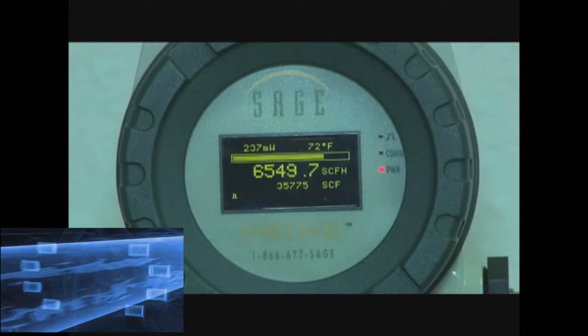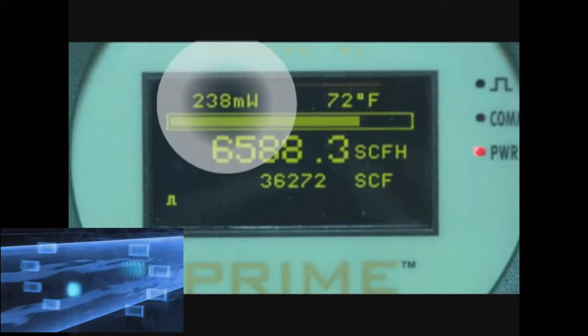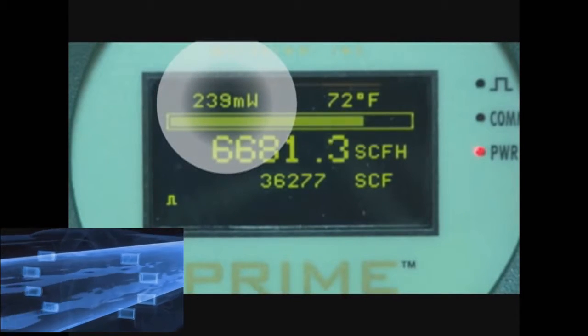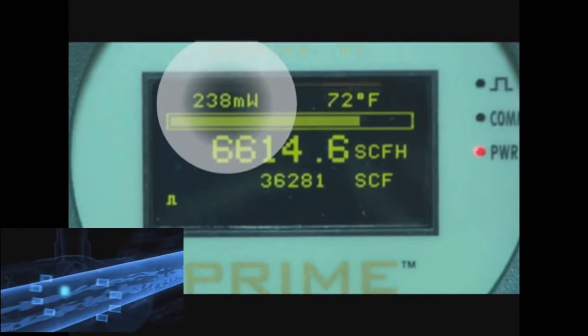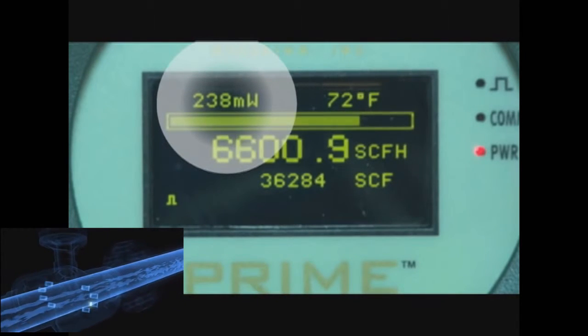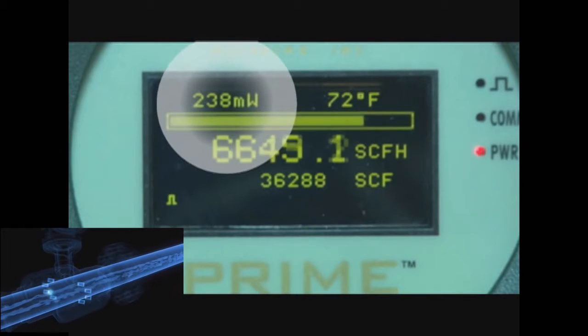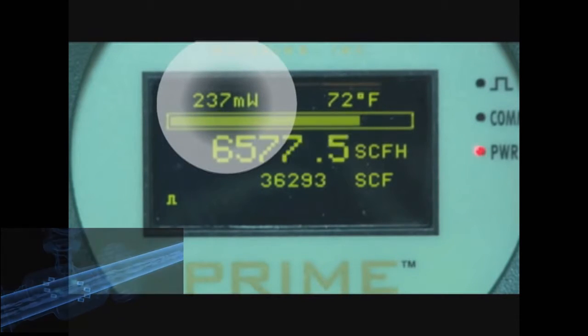In addition, there is a reading in milliwatts in the top left corner, which represents the raw calibration output. It can be used for diagnostics, and most importantly, it can be used to verify the calibration of the insertion flow meter during the calibration process.